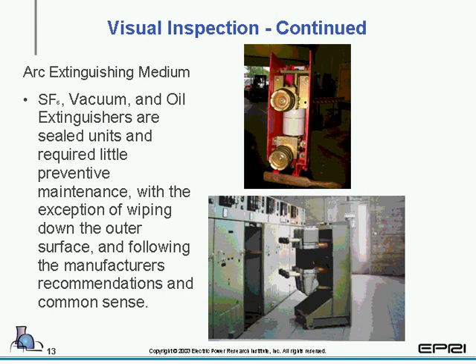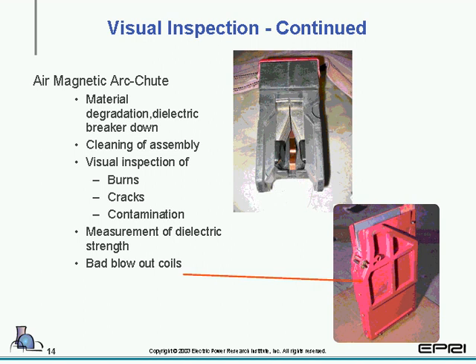We're going to be taking a look at arc chutes or arc extinguishing mediums. Now, when we take a look at the SF6, the vacuum and the oil extinguishing mediums, most of these cannot be seen directly, and you have to gauge their indication of what shape they're in by testing, which will be covered later. Except for, as we'll see on the next slide, air magnetic arc chutes. These can be removed from above or around the contact structures, and you're going to want to take a look for any type of damage, and we have a list of some of the damage that you could see. Some of the most common during the visual inspection are burns, cracks, and contamination.